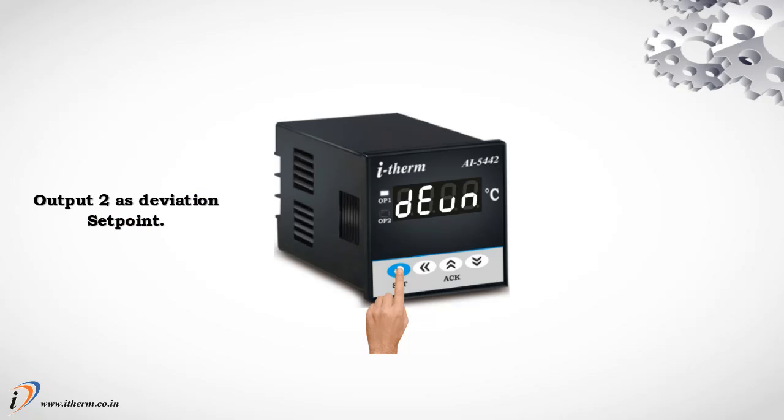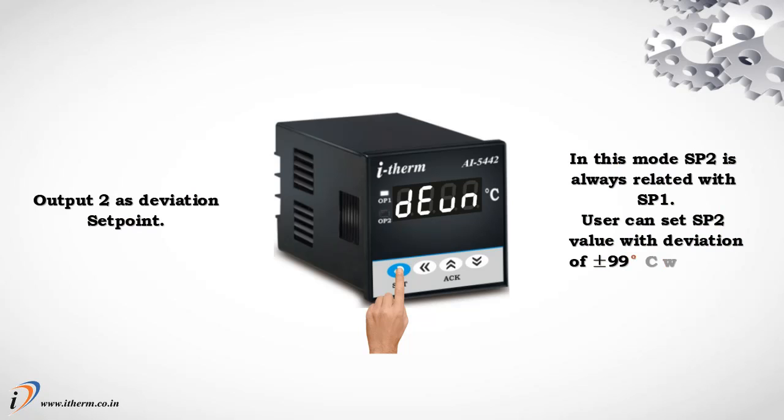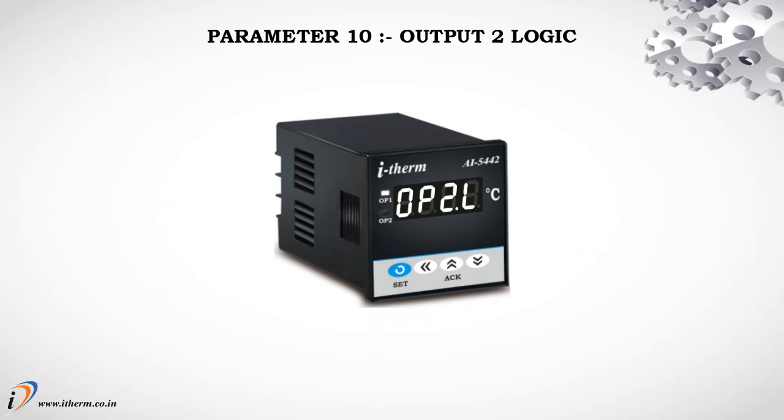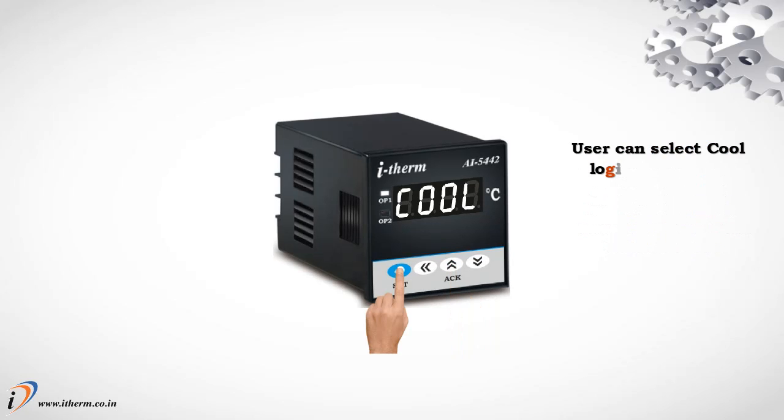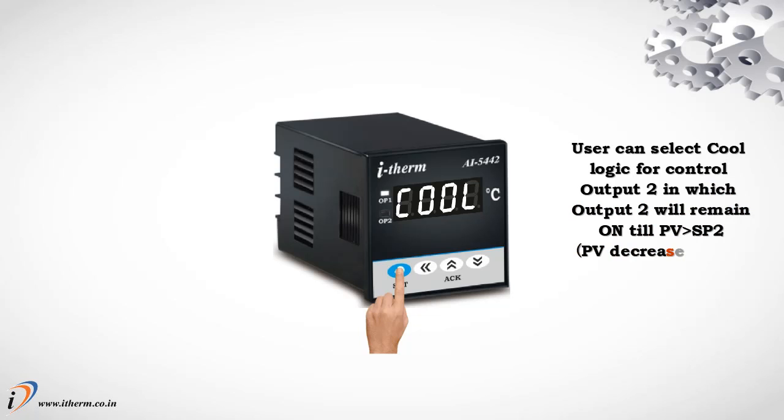Output 2 as deviation set point. In this mode, set point 2 is always related with set point 1. User can set point 2 value with deviation of plus minus 99 degrees Celsius with respect to set point 1. Parameter 10. Output 2 logic. User can select heat logic for control output 2 in which output 2 will remain on until process value is less than set point 2. User can select cool logic for control output 2 in which output 2 will remain on until process value is greater than set point 2.